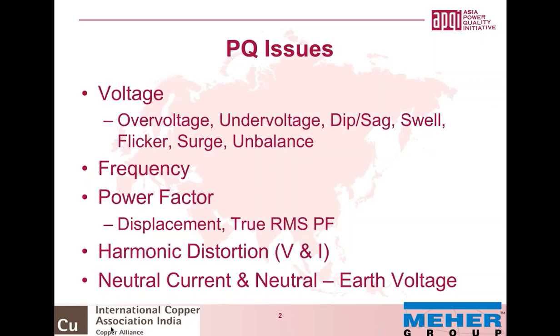The second issue is frequency. This is relatively less of a problem, but we need to tick the box and verify we are comfortable and safe. Generally speaking, frequencies in overloaded or optimally loaded networks will be 50 hertz in our country, or maybe slightly lower. In underloaded networks, it's possible it can go slightly above 50 hertz - a phenomenon noticed in some parts of the country when large power plants are commissioned and demand is lower than supply capability.